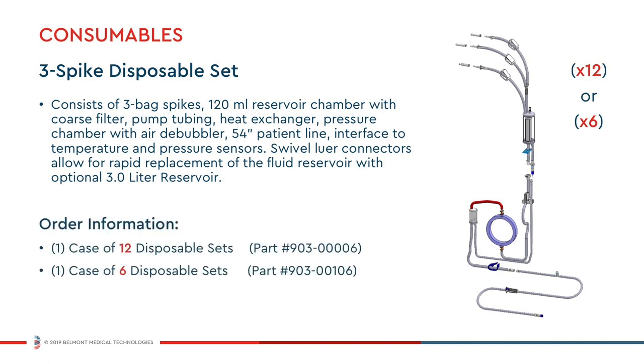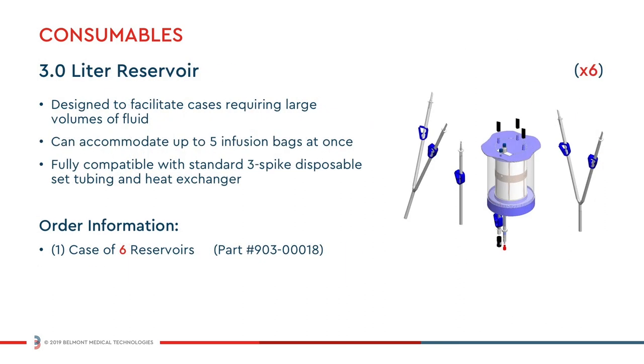The 3-Spike Disposable can now be ordered in two convenient quantities of either 12 or 6 disposables per case. The 3-liter reservoir can accommodate up to five fluid bags at one time and is fully compatible with the standard 3-Spike Disposable Set tubing and heat exchanger. The reservoir can be easily installed before or during a procedure in replacement of the standard 120-milliliter reservoir.